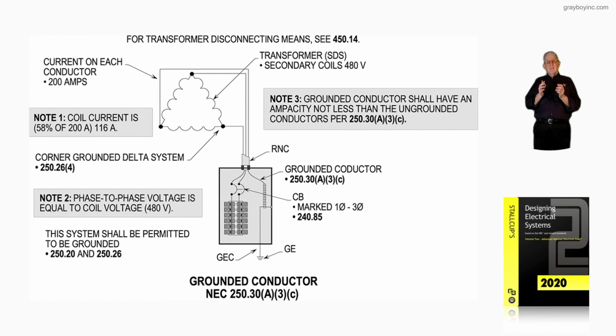But do you see the sections you need to review to get a good handle on the labeling that you put on the panel? If any additional requirements are required there, such as for an ungrounded system, or you have additional requirements for a corner grounded system on your label to let electricians know what type of system they're working on, or performing maintenance, repair, whatever.